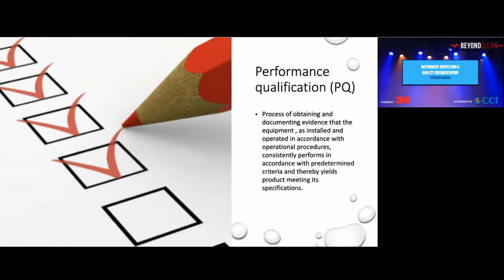what you found. Your sterilizer comes in, they put in the steam, checking the quality of steam. They then figure out that they have to use a BI, Bowie-Dick. They use clinically relevant, evidence-based products according to the manufacturer's installation and what's in the standards. They commission it. They say it's ready to use. And then what do you do? You use those same tests that they did in the IQ, OQ, and your PQ.